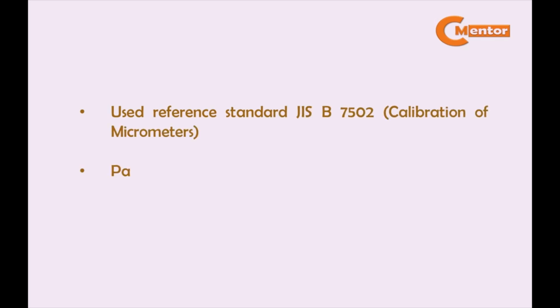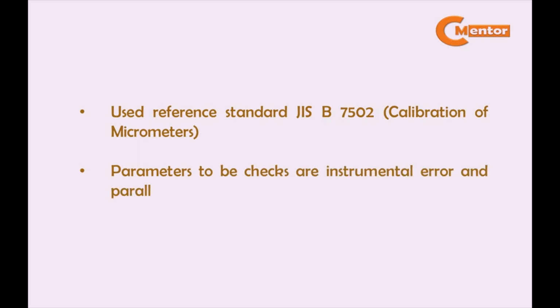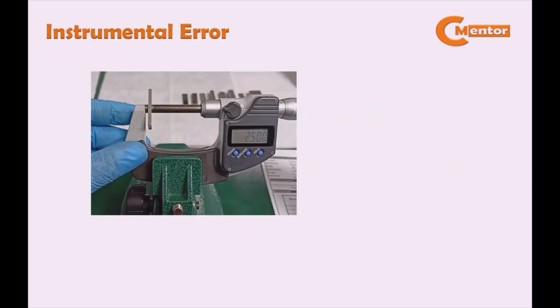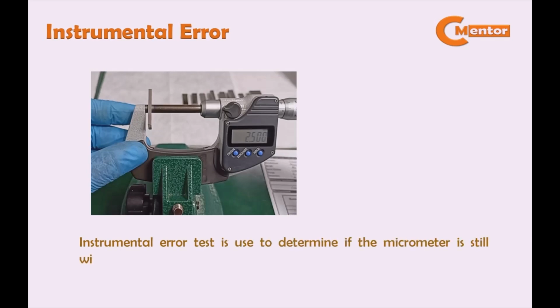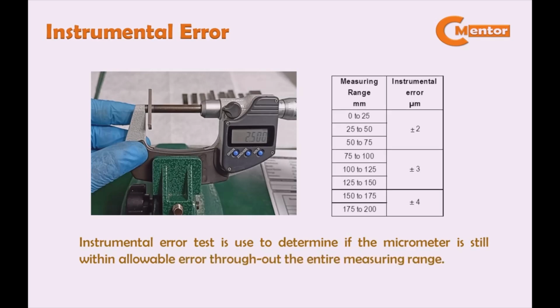Use reference standard JIS B 7502 for calibration of micrometers. Parameters to be checked are instrumental error and parallelism of the measuring face. Now we proceed to instrumental error. The instrumental error test is used to determine if the micrometer is still within allowable error throughout the entire measuring range. You can see the measuring range of the micrometer and the instrumental error based on JIS B 7502.